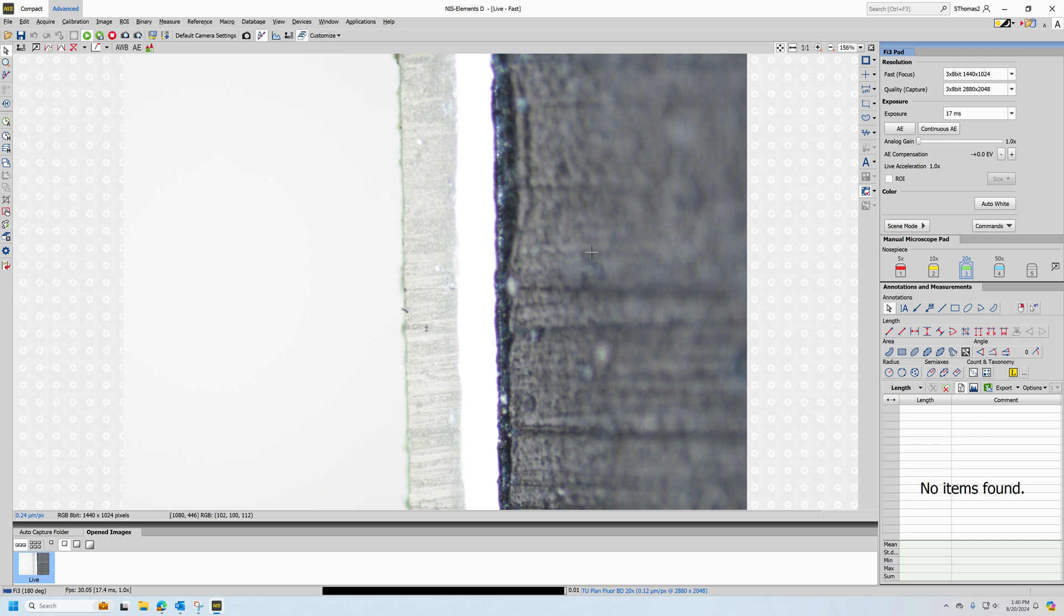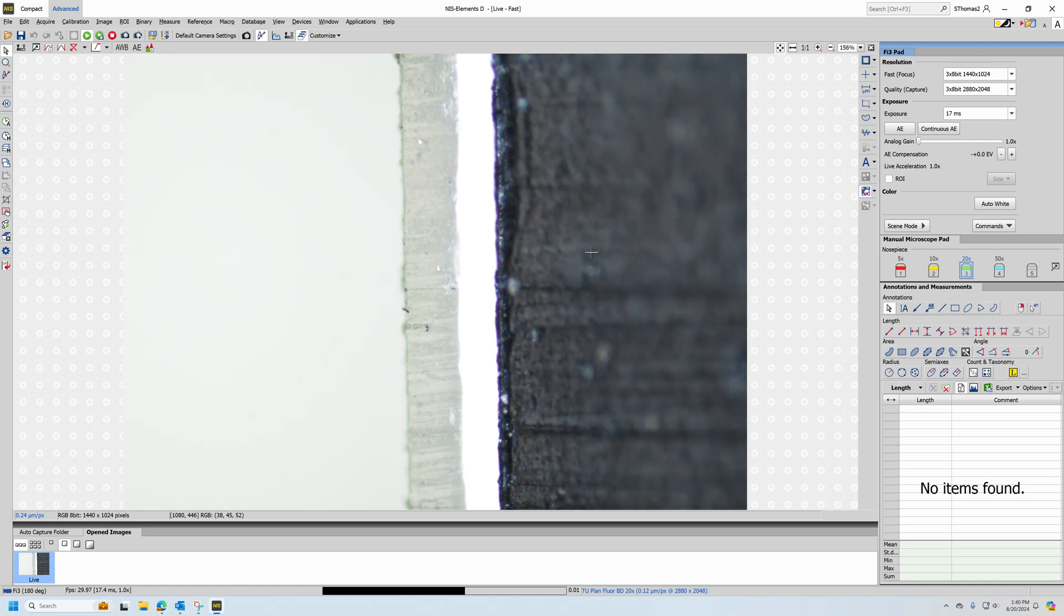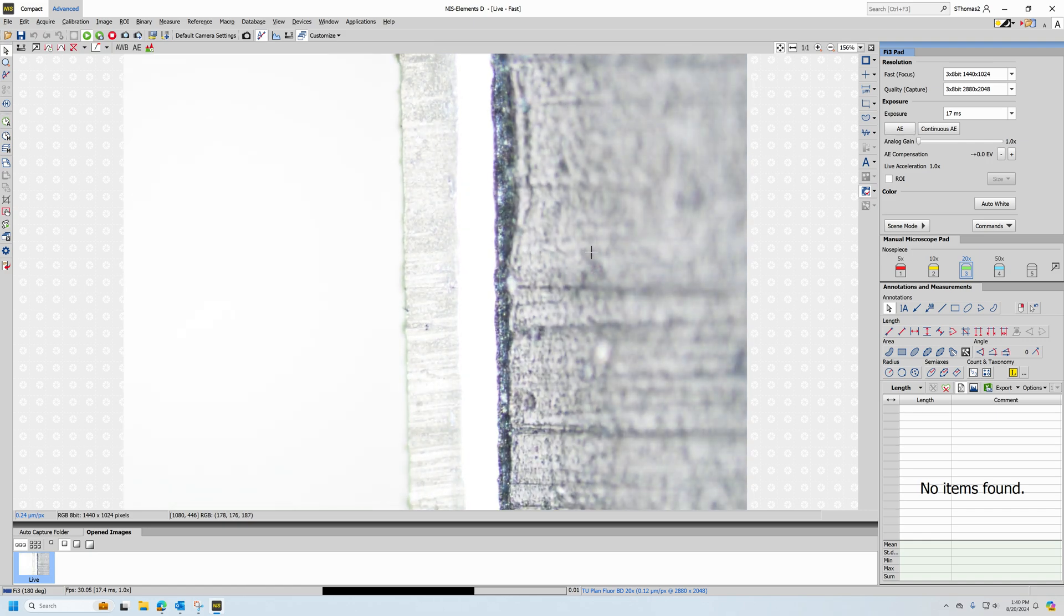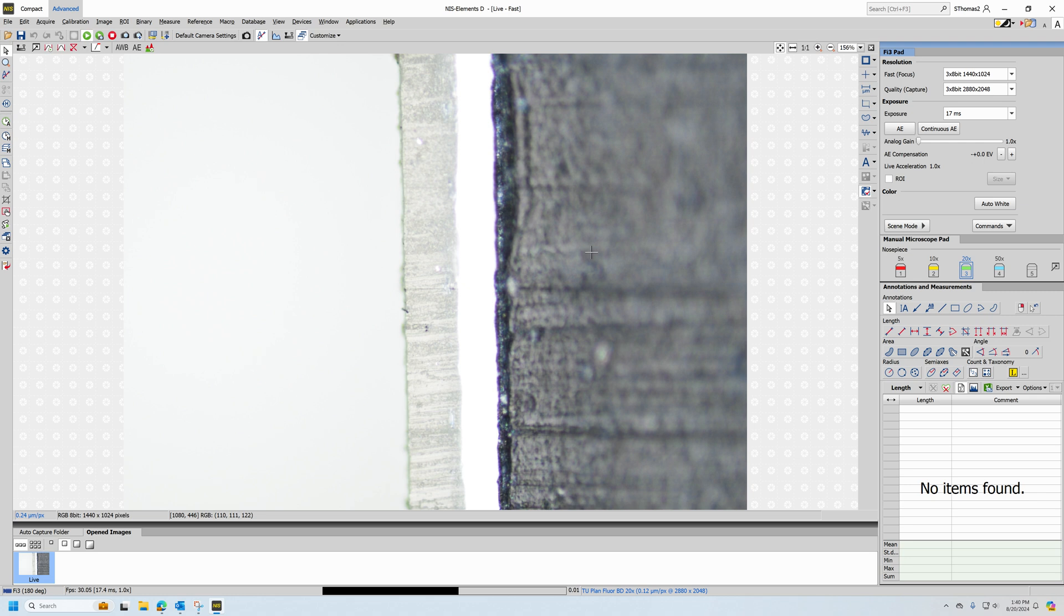Additional adjustments can be made to external lighting, lowering, increasing, or rotating the built-in polarizer that's in the epi illuminator. Various controls can be done outside of the Elements software to improve the overall image effect.